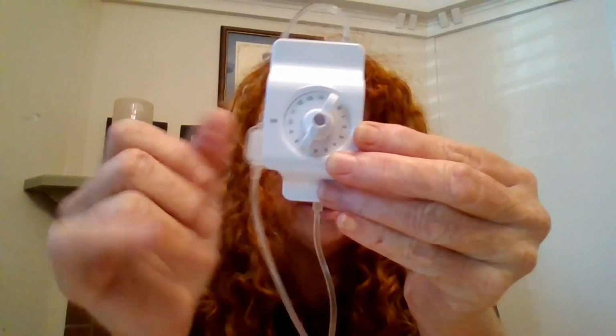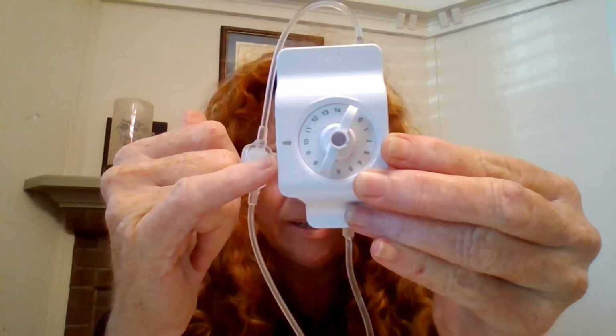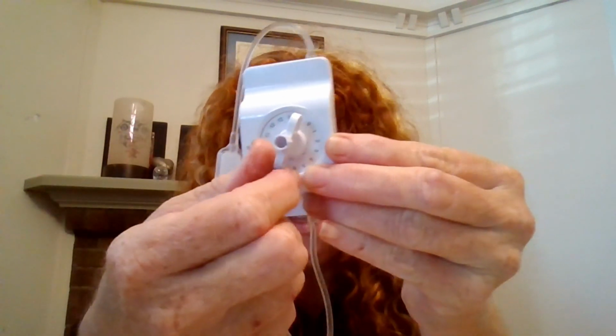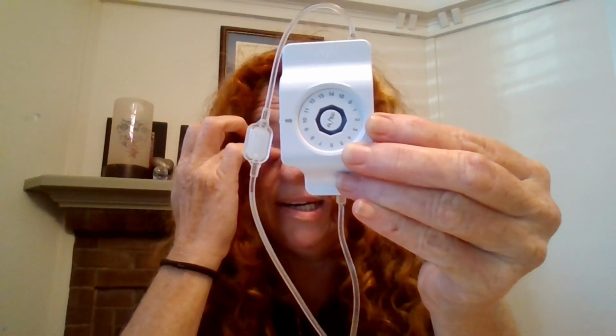So I have now lined that up so that you can see that it is lined up to 10 mils an hour, and then the key is removed. Now that key needs to remain or end up with the nurses on the ward. It is not to be left with the patient at all. Then upon priming of this device, you will open the cap, and when you see your first drop of fluid, which I'm seeing now, you are fine to connect it to your catheter.